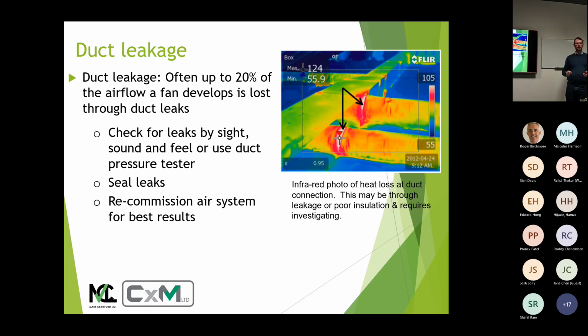When you test it, you'll find it's leaking all the way along the longitudinal seams, all the way around the flanges, out of all the joints. The clips are not in place properly, so it's leaking out of those. So it's just poor manufacturing, poor installation. So now, please just ask to do some random duct tests on all the systems. Doesn't matter how big or small it is.